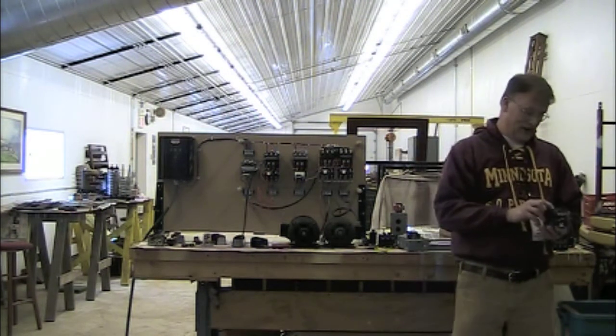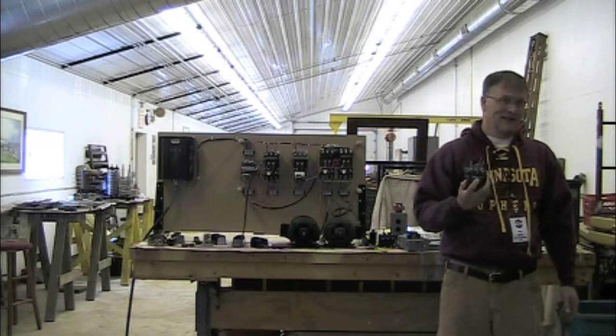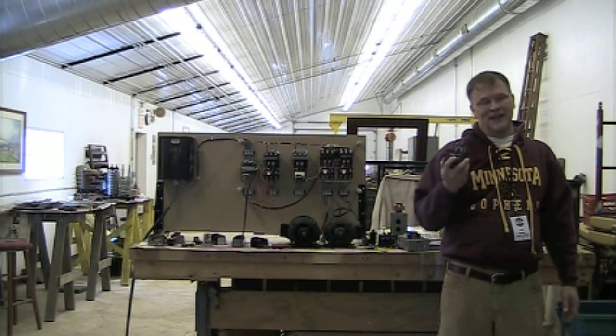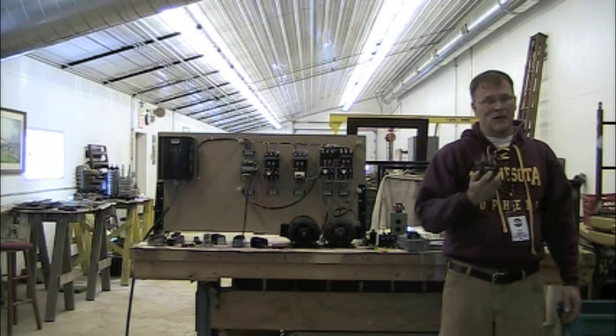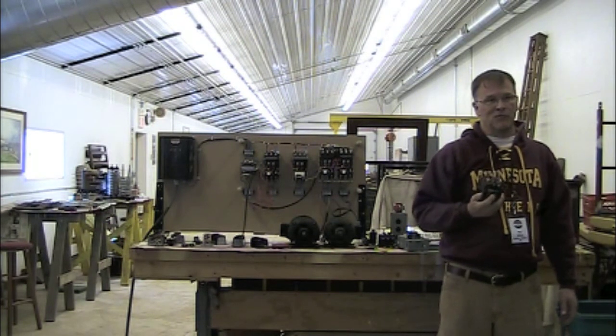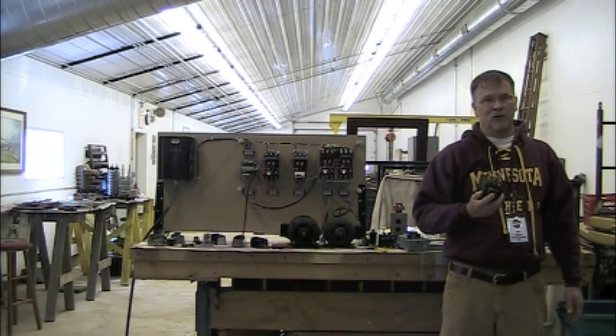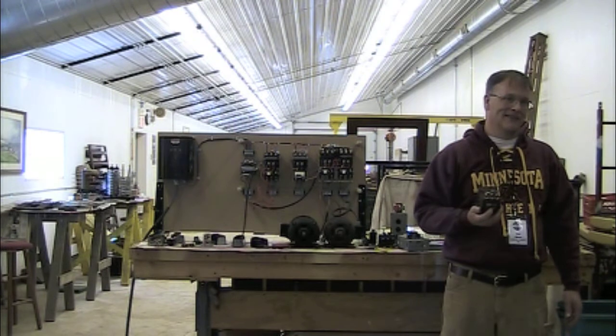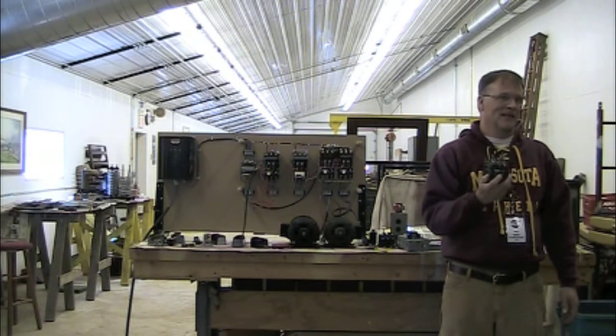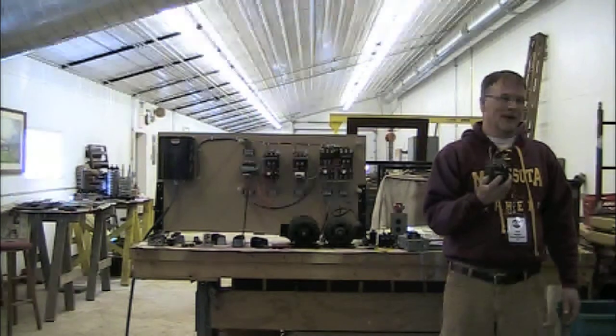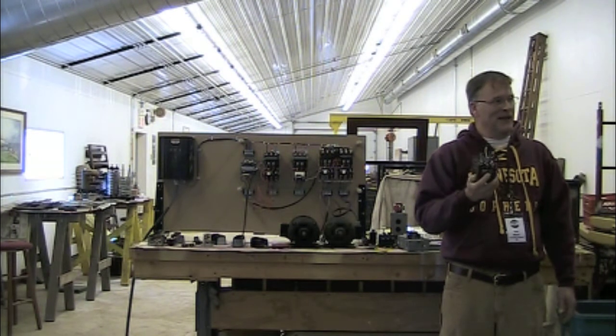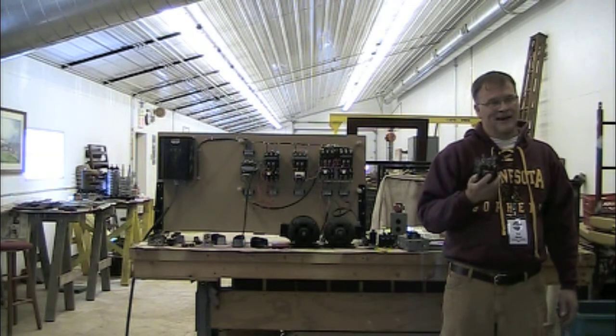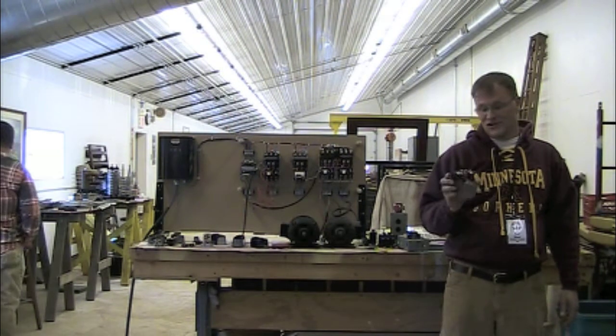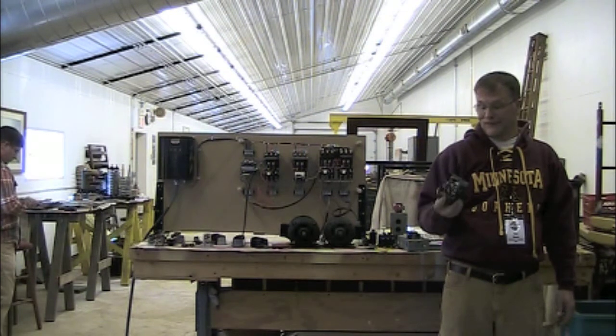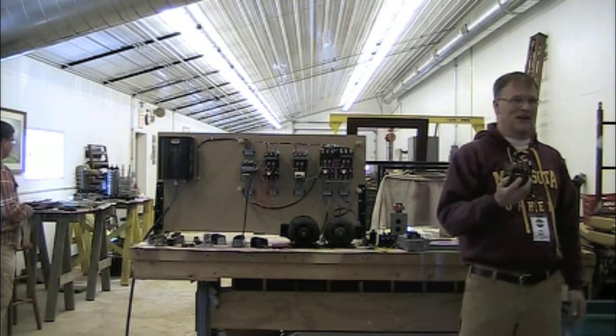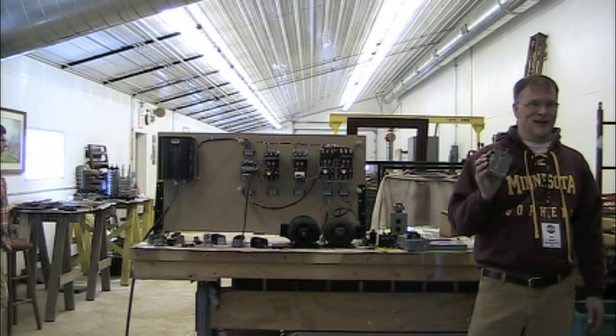But it's funny, I was reading on Square D's website about definite purpose contactors, and they were actually approached by the HVAC industry. They wanted something cheap. They didn't see the value of putting a NEMA contactor on something that was going to outlive their equipment by a factor of 10. So these are cheap. They're not meant for a long lifetime, but they were specifically designed by the manufacturer for a low price point to fit that niche. You can use them for stuff, but I never find much value in these.